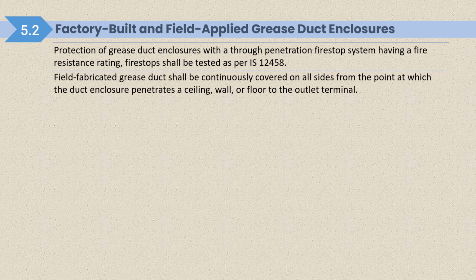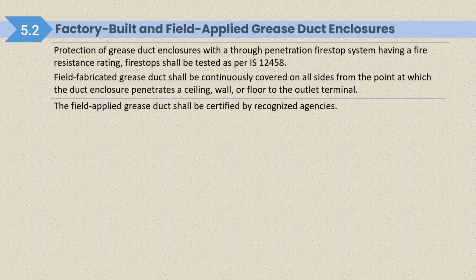Field fabricated grease duct shall be continuously covered on all sides from the point at which the duct enclosure penetrates a ceiling, wall or floor to the outlet terminal. The field applied grease duct shall be certified by a recognized agency. So there are two types of duct we are talking about. One is factory built and the other is field applied grease duct that is getting assembled at the site.